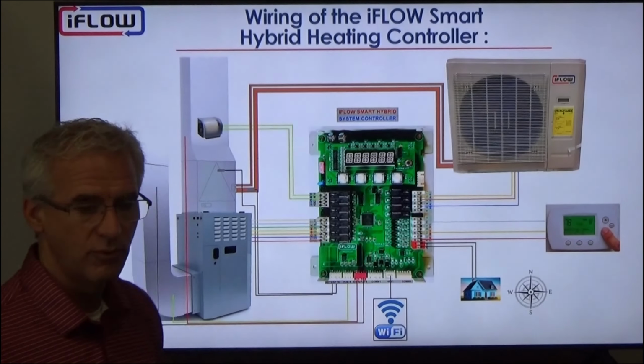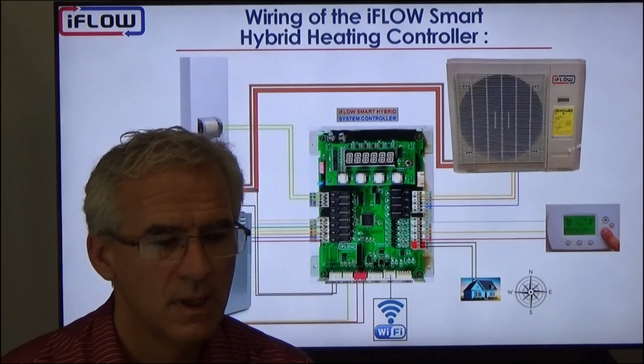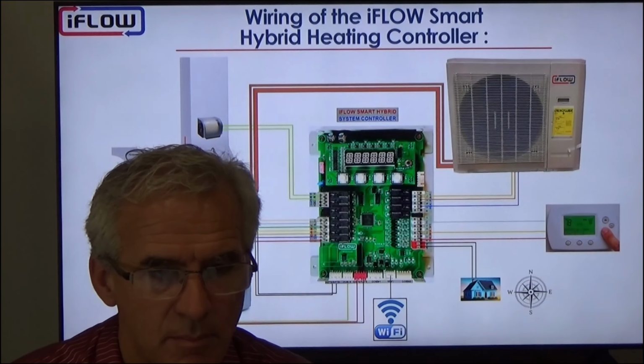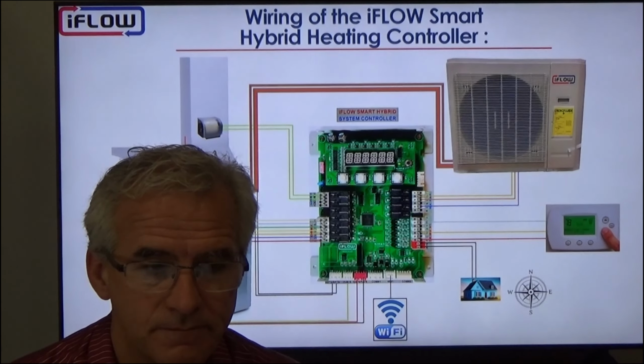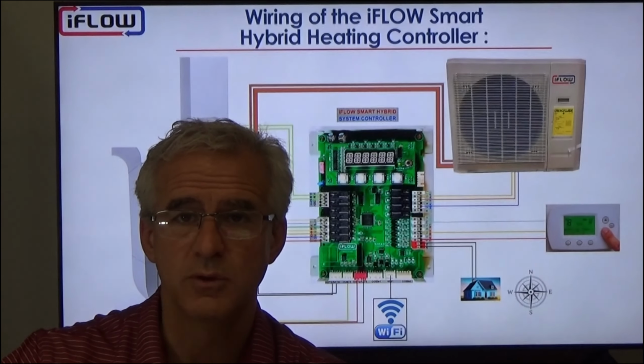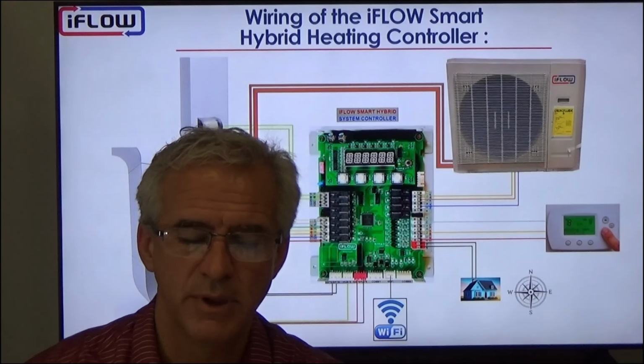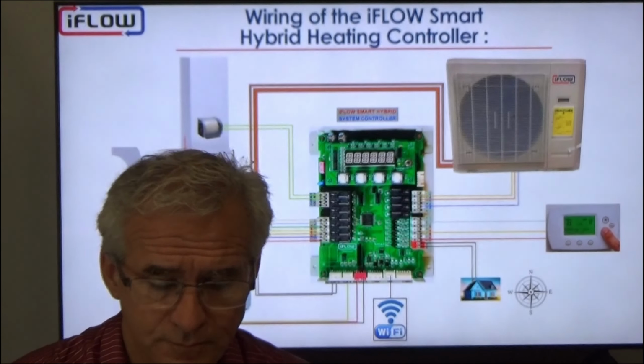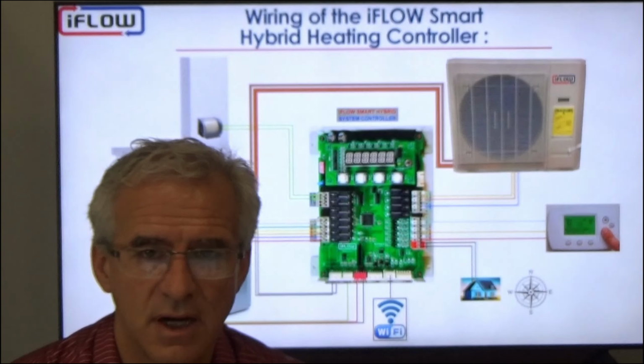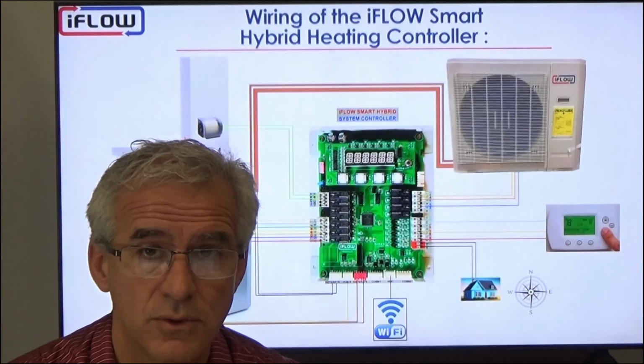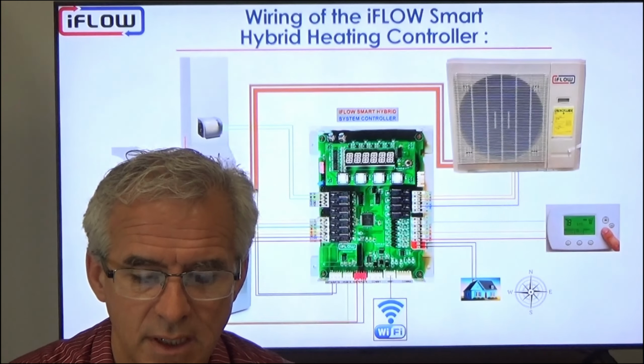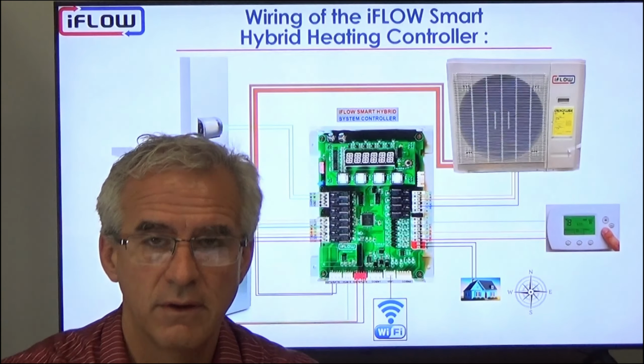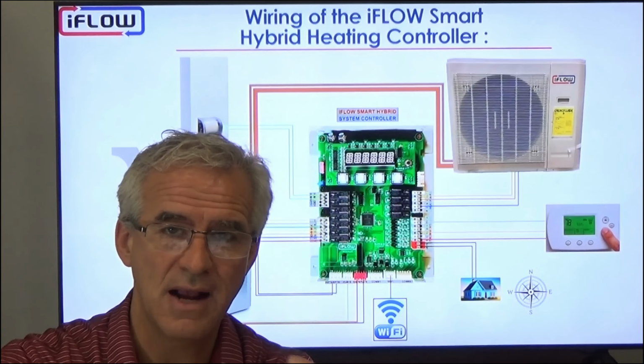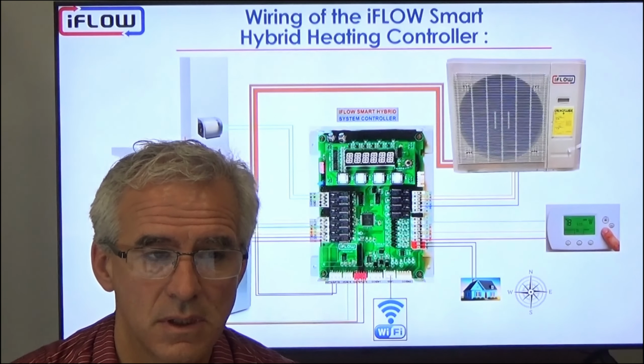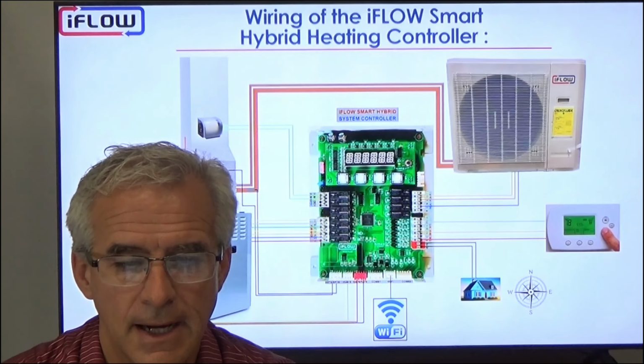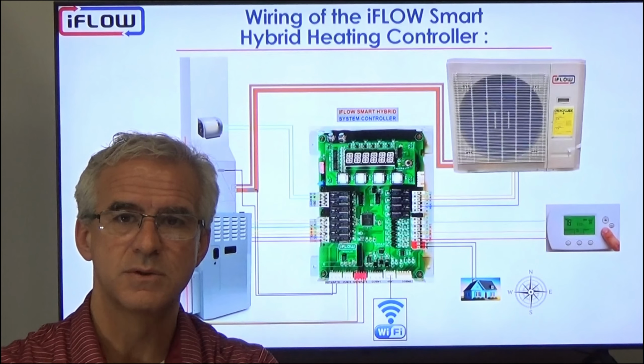Typically, we run the heat pump in September, October, November, when the loads will be low and the gas appliances would typically be cycling a little bit. And we get the advantage of the higher COPs during those shoulder seasons. Then once we get into December, January, February, the ability of the heat pump to extract heat from the colder outside air is a little more difficult and COPs will drop a little bit. Then we could switch over to the gas side.